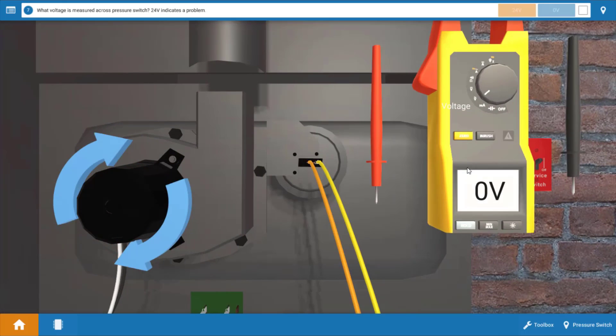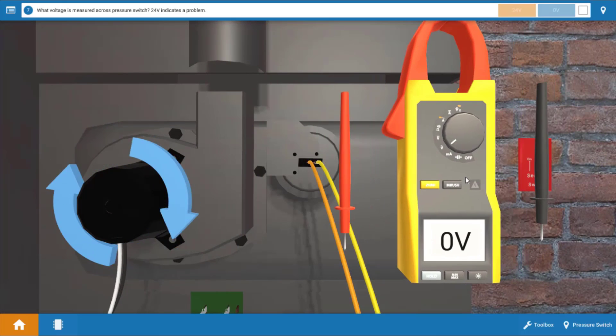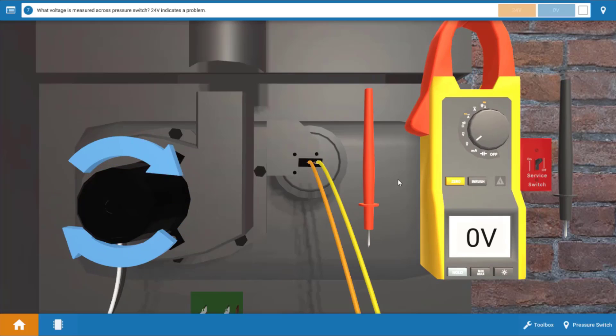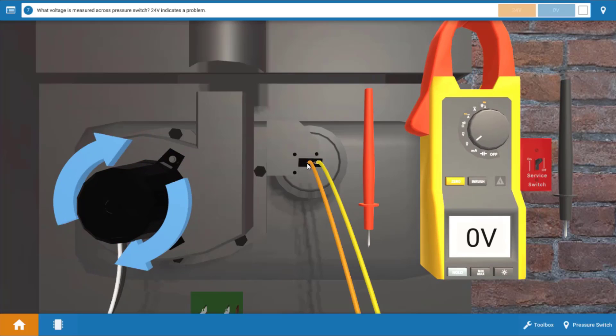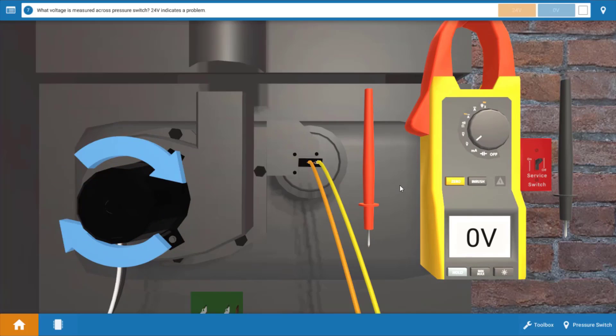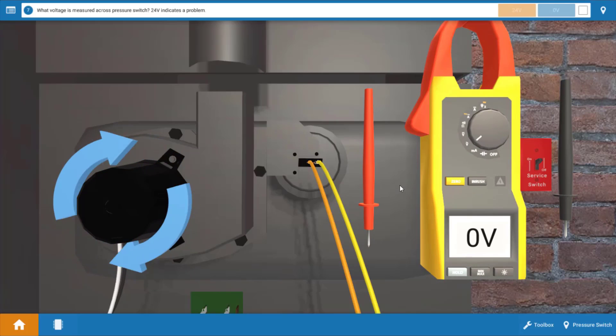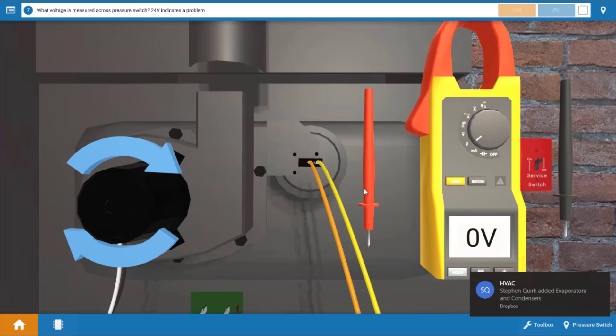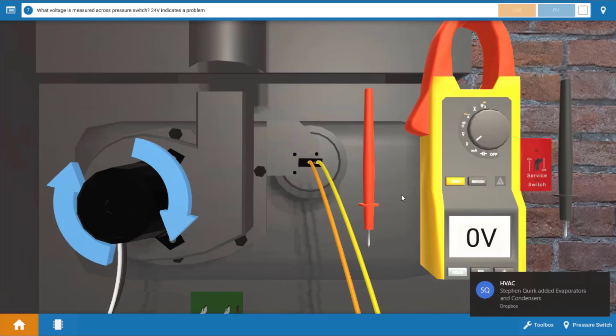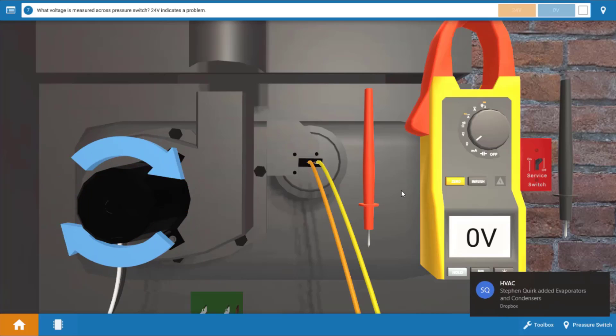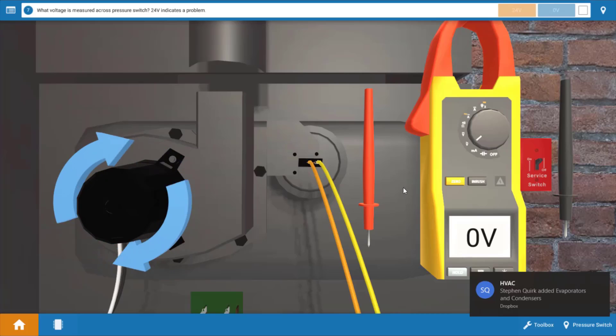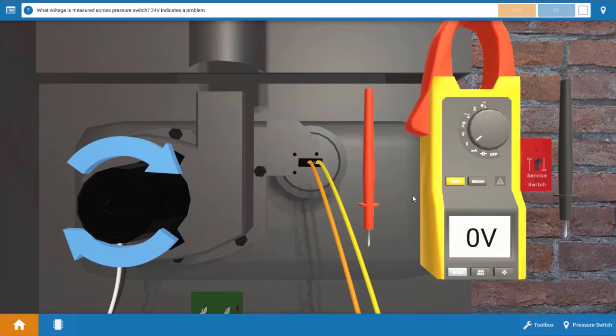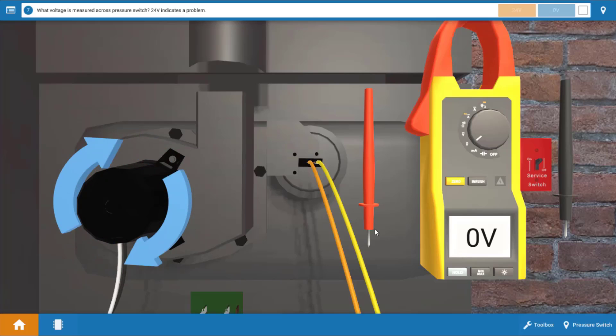Now before we assume we have an issue with the igniter we need to verify that the pressure switch right here closed its contacts. The pressure switch verifies safe combustion airflow and if its contacts don't close the IFC will not even send power to the igniter.